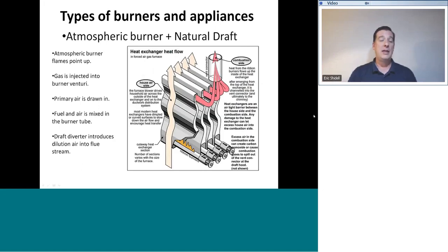Natural draft appliances utilize a heat exchanger that's essentially open on both ends. So at the bottom of the heat exchanger, burners are installed. Here's just a tube with an opening in it. That's a venturi. Air is going to be drawn in through those openings, and the flames appear here. All atmospheric burners feature flames that point upwards. Your cigarette lighter is an atmospheric burner.